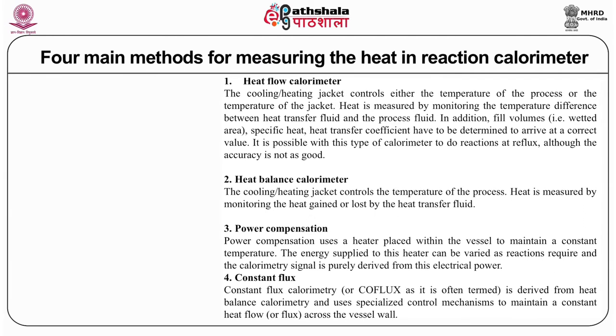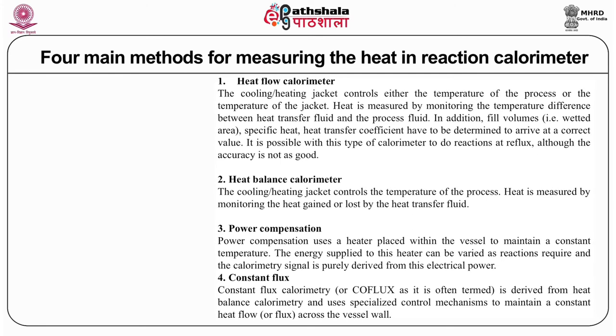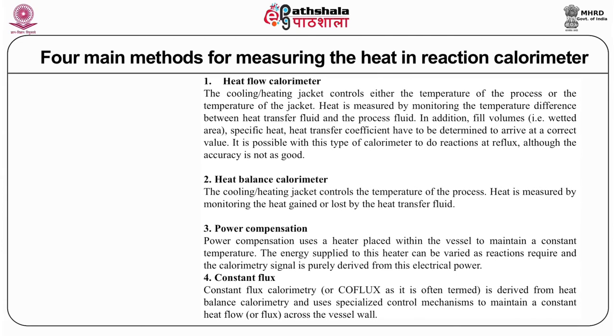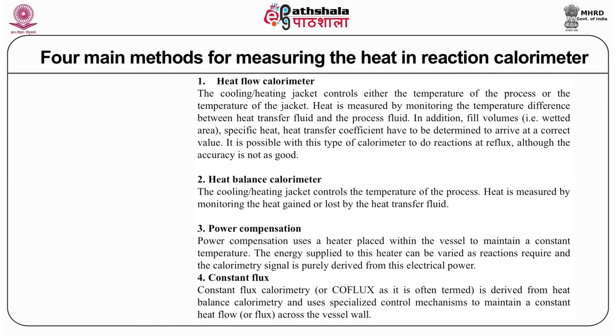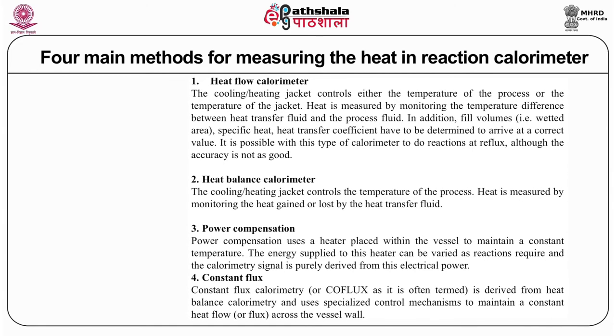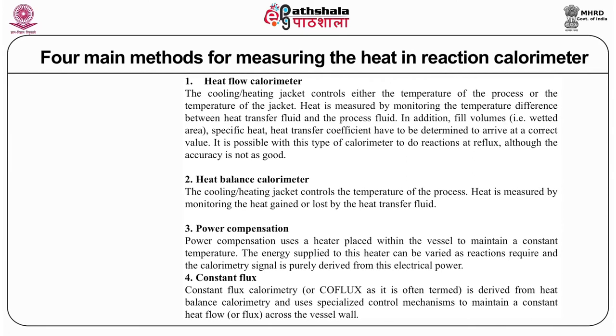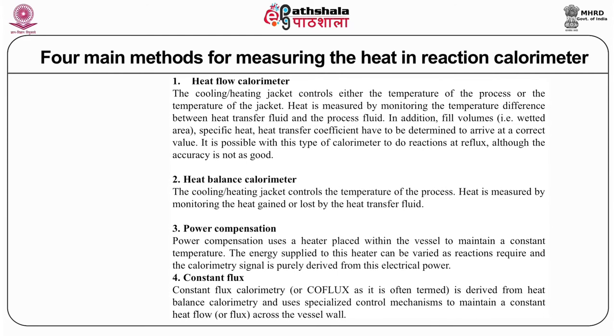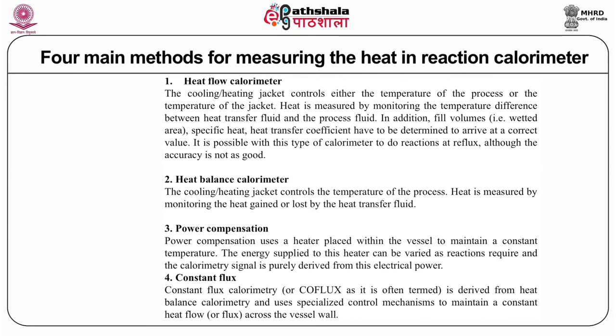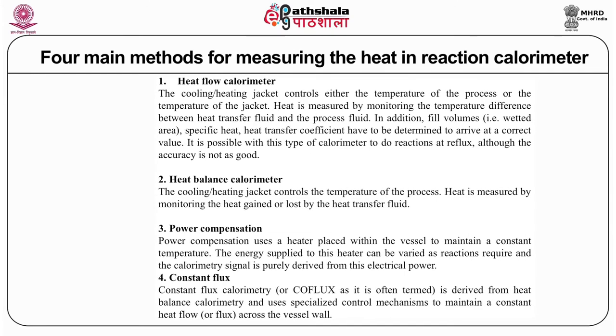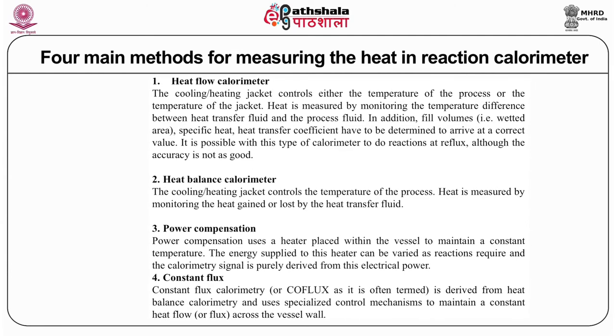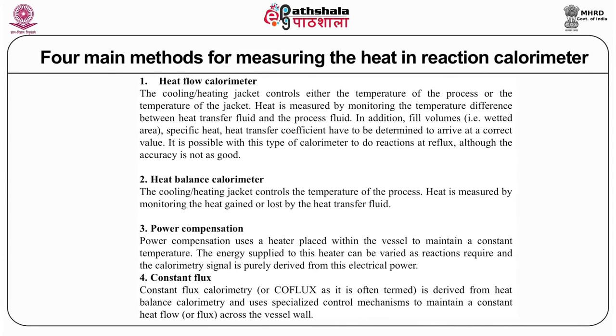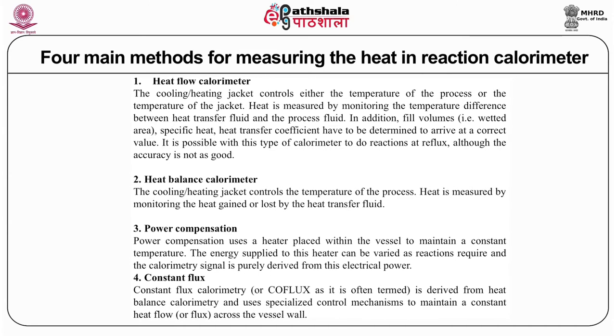There are mainly four types of reaction calorimeters. The first is the heat flow calorimeter, where a cooling or heating jacket controls either the temperature of the process or the temperature of the jacket, and heat flow is measured by monitoring the temperature difference between the heat transfer fluid and the process fluid. Fill volumes and specific heat and heat transfer coefficient also need to be determined. It is possible to do reactions at reflux with this type, although accuracy is not very good.